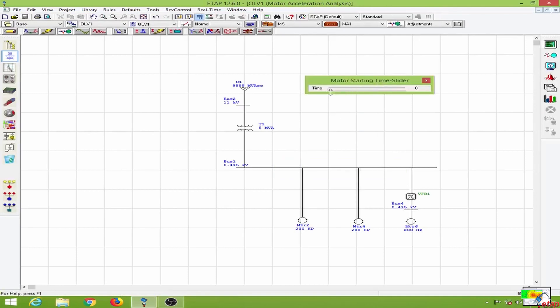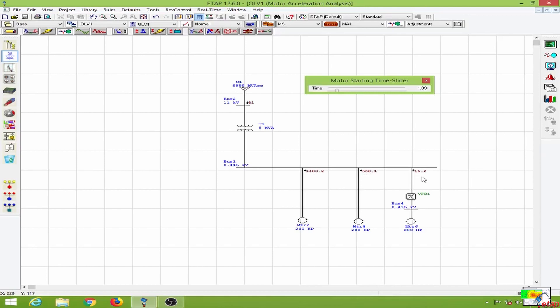The motor time slider appears over here, so let me go to the 1-second mark. You can see the inrush current for various starters — motor 2 does not have any starter so this is its inrush current, whereas motor 4 having the autotransformer starter has 663 amps of starting current. For the V/F drive, the starting current is much lower and varies gradually as you can see the change in currents drawn after the starting period.